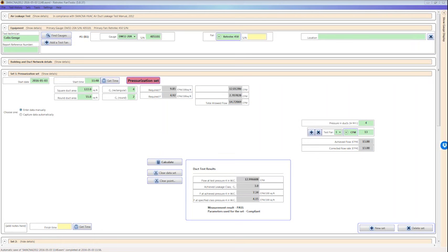Well, the other part of that is that the extrapolation feature you have based your gauge on is an industry standard, not just something that Retrotec has internally created. It is a common way of extrapolating. Correct? Well, we're actually using the SMACNA formula for extrapolating, which uses an oddball exponent, and we use the same thing. We actually agree with their approach, and it works quite well.